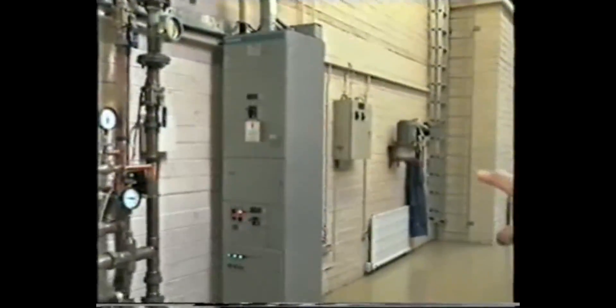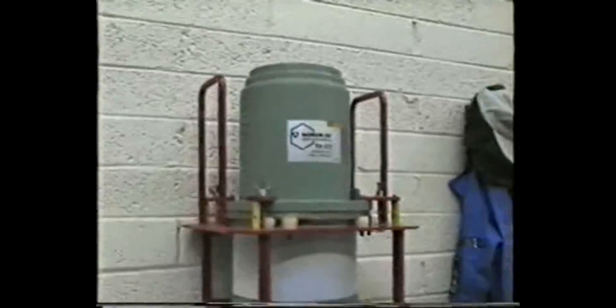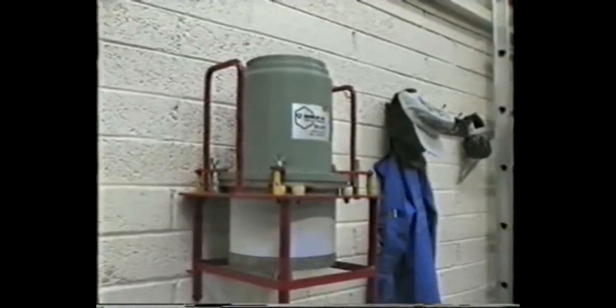That great cabinet there is motor control. It controls all the pumps and blowers in the plant room, cooling blowers. And it also controls the switching of the combining unit. There are motor-driven switches on the top of this combiner. And this being the combiner here. One quality tube. Are tubes expensive? 30,000 pounds each. They are guaranteed for 5,000 hours, but normally we get in excess of 40,000 hours out of them.